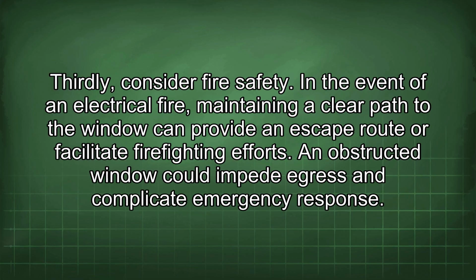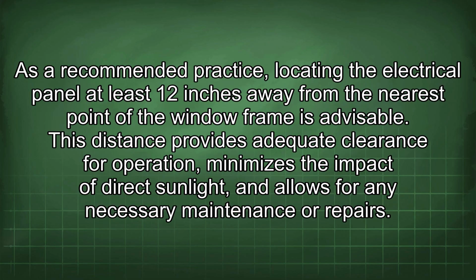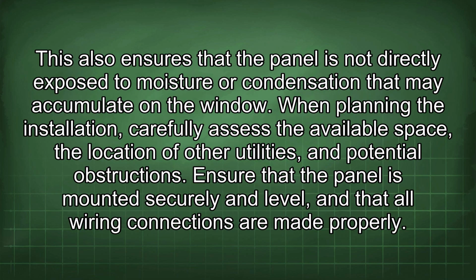Thirdly, consider fire safety. In the event of an electrical fire, maintaining a clear path to the window can provide an escape route or facilitate firefighting efforts. An obstructed window could impede egress and complicate the emergency response. As a recommended practice, locating the electrical panel at least 12 inches away from the nearest point of the window frame is advisable. This distance provides adequate clearance for operation, minimizes the impact of direct sunlight, and allows for any necessary maintenance or repairs. This also ensures that the panel is not directly exposed to moisture or condensation that may accumulate on the window.